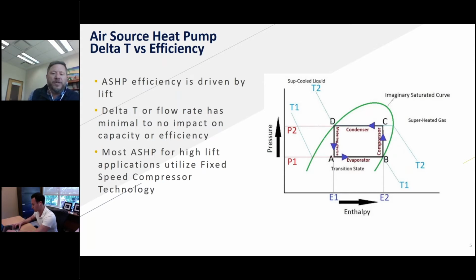So the greater the differential between the evaporating temperature, or suction temperature, which I'll just call the low side of the system, and the high side of the system, the greater the lift, and the more work we have to do. That's a direct reflection of our efficiency. Anytime we can drive the low side and the high side closer together, the compressor has to do less work, which makes us more efficient. If you've ever looked at efficiency curves for an air source heat pump, that's why you would see, at elevated ambient temperatures and fixed hot water temperatures, say I'm trying to make 120 degrees, more efficient operation at 20 degrees than at 0 degrees. Likewise, 40 degrees is going to be more efficient than 20, and of course than 0. So when we think about our air source heat pumps, we're really talking about how to optimize the system to minimize lift whenever possible, to make it as efficient as we can.